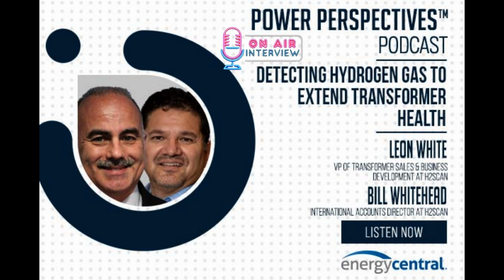Sure, thank you. So most transformers, larger transformers and small transformers, whether they're on a pole near your house or in the front yard or in a substation, most are filled with mineral oil. And when transformers get sick and things start happening inside the transformer, temperatures inside can reach usually 150 degrees C or hotter. And when you start seeing those temperatures, the oil starts degrading and starts generating hydrogen and other combustible gases. And so those are bad things to have in your transformer.